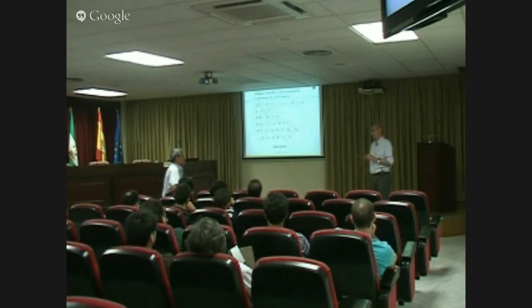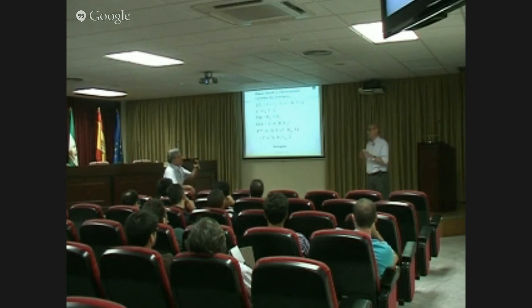What we do is create an artificial bus and turn it into a branch with an artificial impedance. Because anytime you have a current, you also have the sending end voltage—we don't have separate, standalone current measurements. Typically when a current measurement comes, it comes with the sending end voltage, even if it belongs to another area—maybe not, if you cut the region.